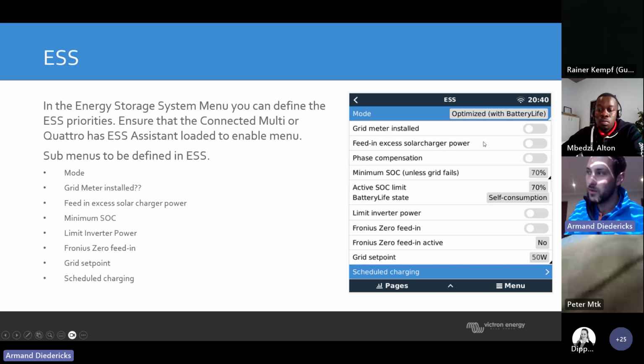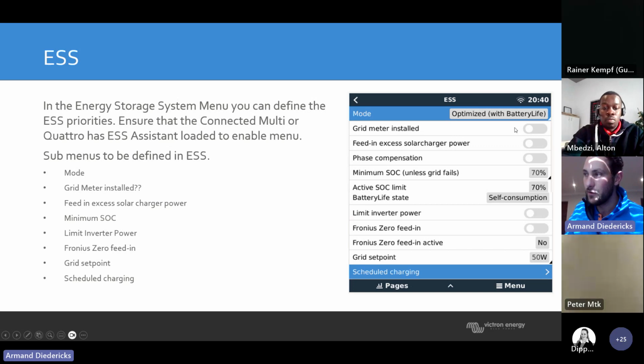Grid meter installed, you enable or disable the grid meter. But once you enable the grid meter and there's no grid meter installed, it won't charge your battery. It won't allow Eskom. So just ensure that if you have an energy meter installed, it is activated. If you don't have one, it is deactivated. Then whatever the parameters are, whatever the site diagnostics are, you set the parameters according to that.